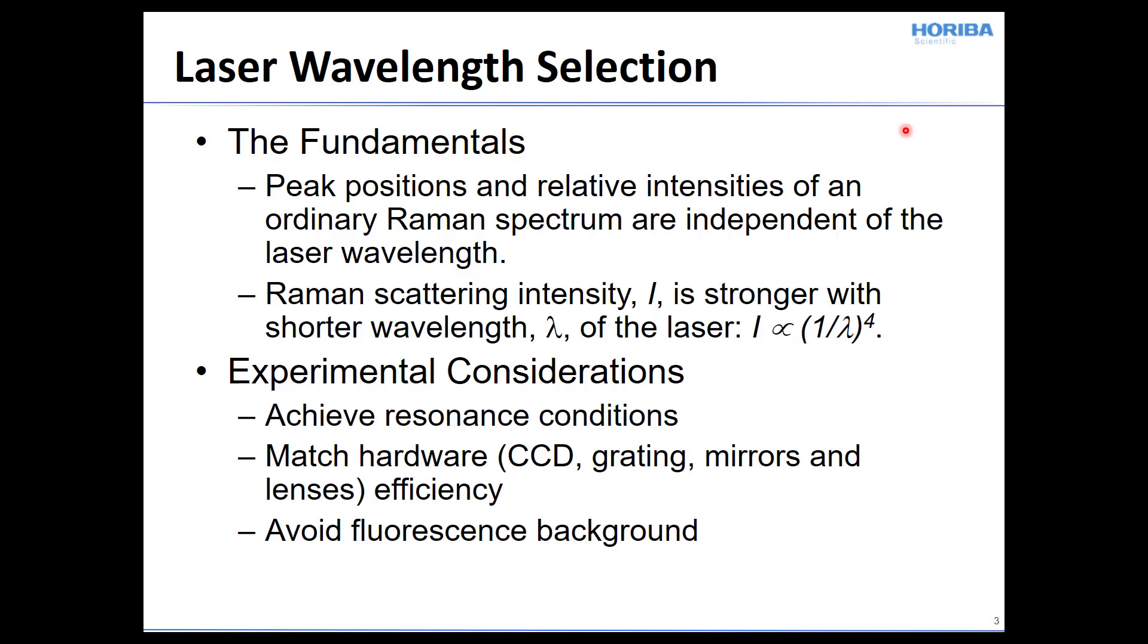Furthermore, you want to make sure that your laser wavelength matches the hardware efficiencies of, say for example, your CCD, grating, mirrors and lenses, that is to say their dependencies on wavelength and the efficiencies as a function of wavelength. And finally, one of the things to consider in selecting an excitation wavelength is avoiding the fluorescence background, which is a topic for this video.